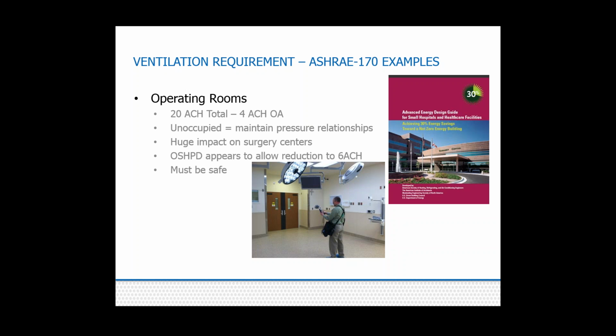It can have a huge impact on energy use, especially, I put up a graphic here of the Advanced Energy Design Guide for small hospitals and healthcare facilities. In that guide, when we added the recommendation that ORs set back, and I think we picked 4 air changes as being enough to maintain the pressure in that case, it took us from being a 30% savings guide to making over 40% savings in every climate zone except Alaska. So it has a huge impact on the energy use of those spaces. My quick reading of the OSHPD regulation is that they would let you go down to 6 air changes.